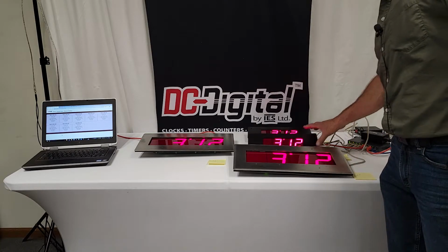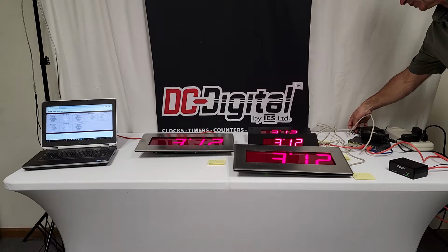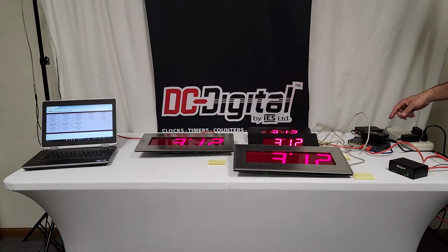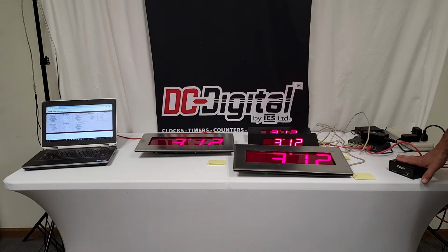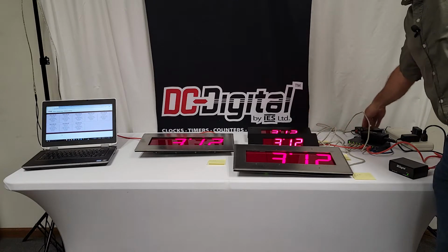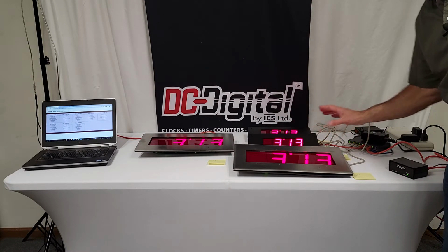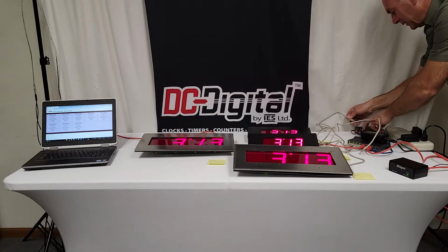But if you lose your NTP server, it would give you an error on the display. You're going to get a flashing LED here, and you're going to get a failure on your web page. Each individual clock has its own web page, reporting back to the server and pulling up to the new web page that he's developed. I've disconnected the NTP server, and we're getting the flash, but we're still getting accurate time. It's keeping time on its own, with a failure on the web page for your individual clock. I'm going to go ahead and reconnect the NTP server.